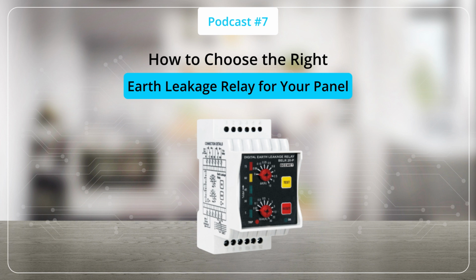The CBCT detects this imbalance and sends a signal to the ELR. If the leakage current exceeds a predefined safe limit, the ELR reacts immediately. It activates its output contacts, which then trigger a circuit breaker. This is often achieved by sending a signal to a shunt trip coil or an undervoltage release coil connected to the main circuit breaker.